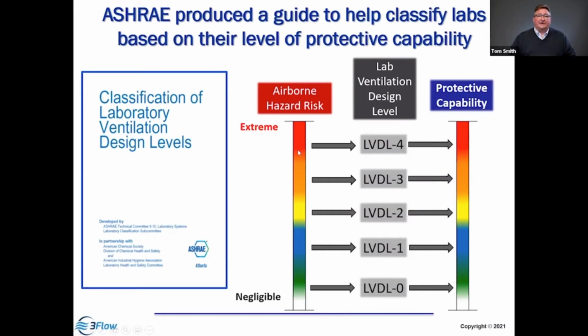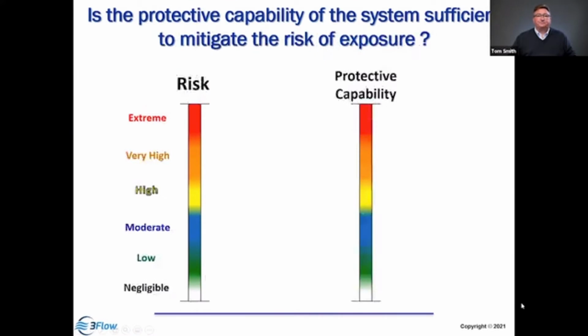So if you look at the level of risk, if they're working with low to no hazards, they don't require a lot of protection. But if they're working with chemical warfare agents, they're going to require the highest level of protection. So we want to make sure that the hoods are appropriate and the ventilation systems are appropriate to provide the required level of protective capability. And we call that the lab ventilation design level. So let's say that we go into a laboratory and we look at the associated risk based on the application from negligible to extreme.